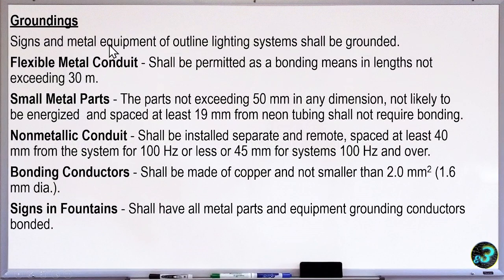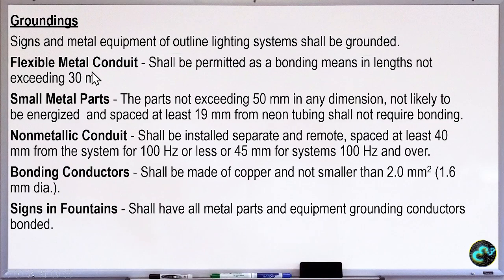Okay. Groundings. Signs and metal equipment of outline lighting systems shall be grounded. Dapat, kasi metal, especially they are also put in outdoor locations, so dapat may proper grounding. Okay. Flexible metal conduit. We could use flexible metal conduit as a means of bonding in lengths not exceeding 30 meters. So if you are going to have a connection between metal parts, instead of using wires, pwede nating gamitin ang flexible metal conduit as long as hindi lalagpas ng 30 meters ang length. Small metal parts, the parts not exceeding 50 mm in any dimension, not likely to be energized, and spaced at least 19 mm from the tubing shall not require bonding.